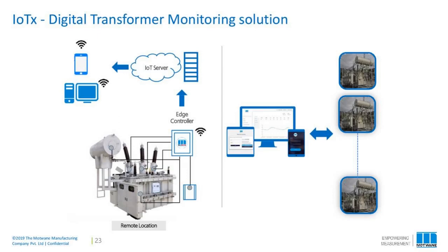But in a broader view, there is data available from the nameplate and other submissions along with the transformer, plus there are governing standards which give a guiding value for those parameters - that's from the design point of view. And then the other part is the dynamic loading, the dynamic condition.